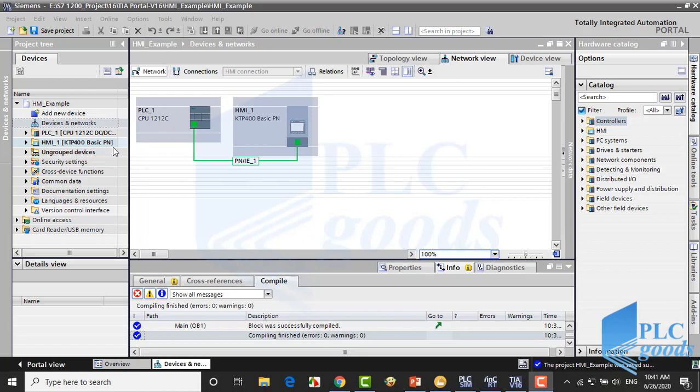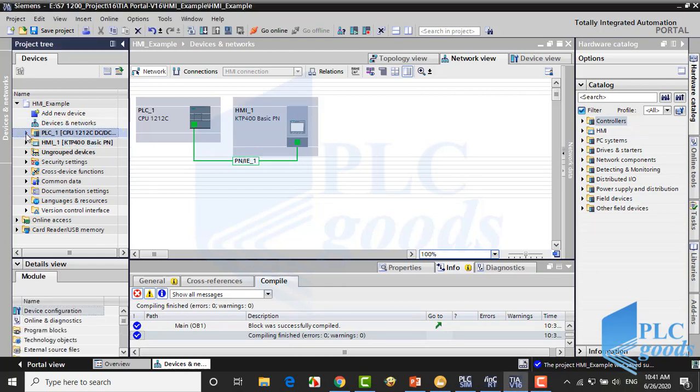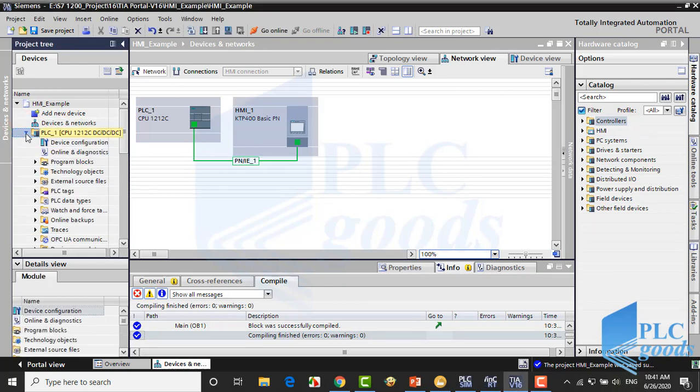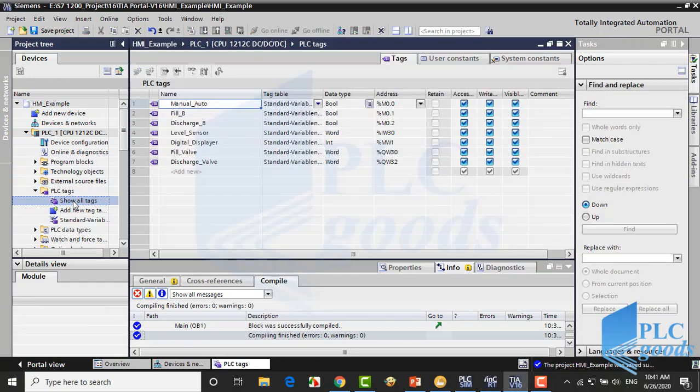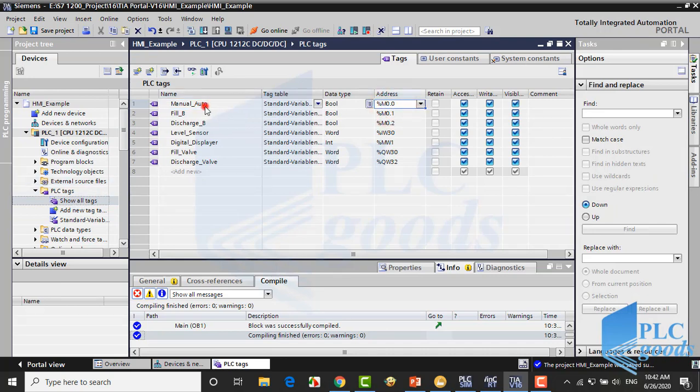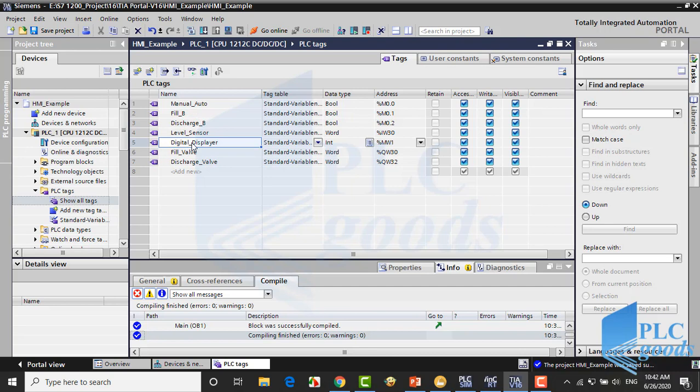In TIA software we have a PLC and HMI which are connected together. Let's see the PLC program tags. Here we have a bit of memory which determines the auto/manual mode. Then two bits of memory are used to turn on valves—these bits are activated by HMI buttons. Next tags are level sensor input, digital display memory to store level liquid based on percent, and two analog outputs respectively: filling and discharging valves.